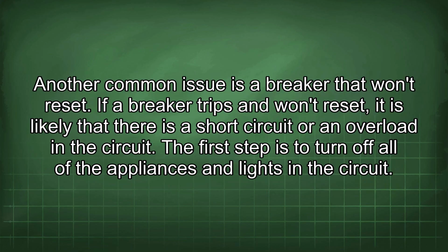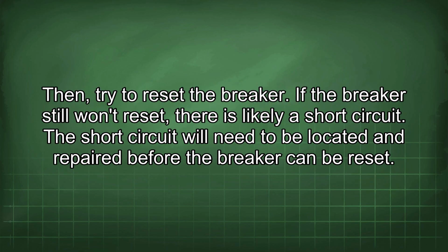Another common issue is a breaker that won't reset. If a breaker trips and won't reset, it is likely that there is a short circuit or an overload in the circuit. The first step is to turn off all of the appliances and lights in the circuit. Then try to reset the breaker. If the breaker still won't reset, there is likely a short circuit. The short circuit will need to be located and repaired before the breaker can be reset.